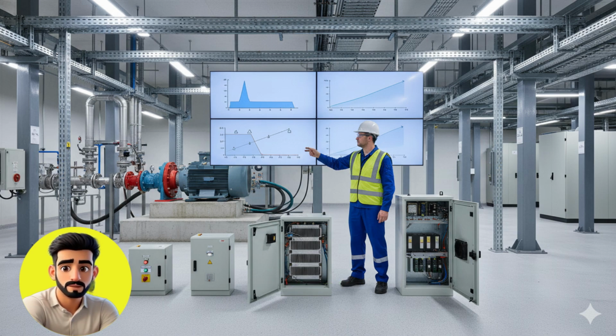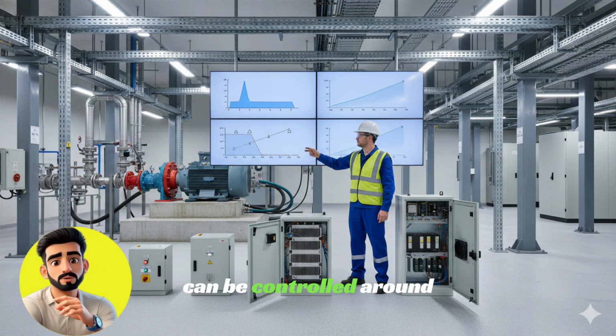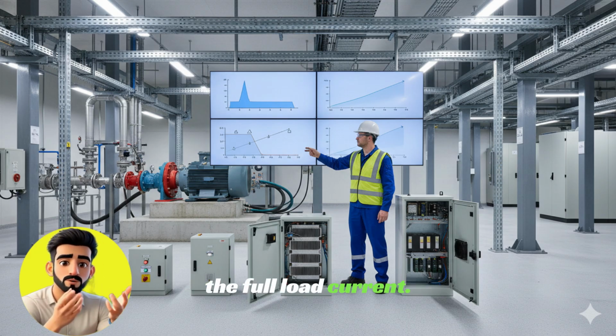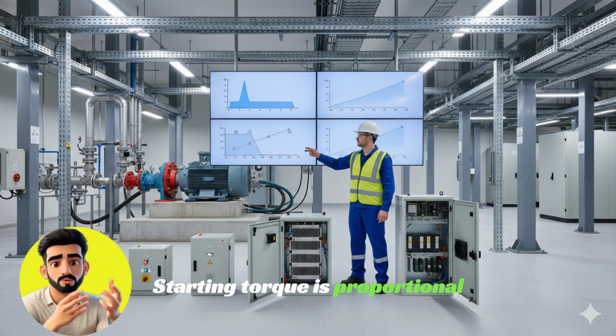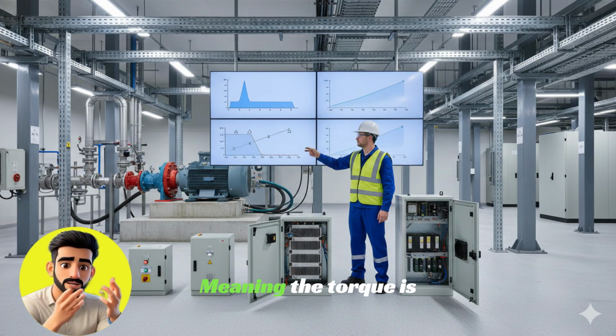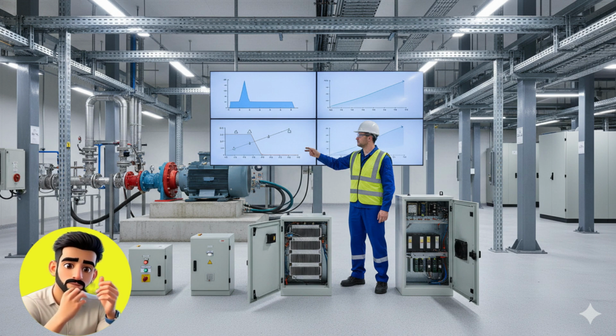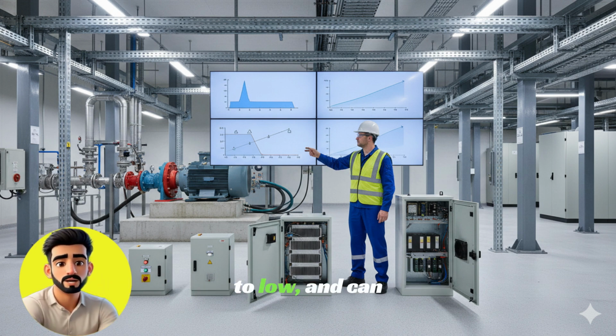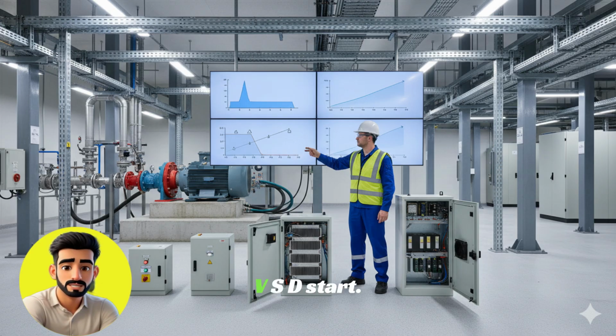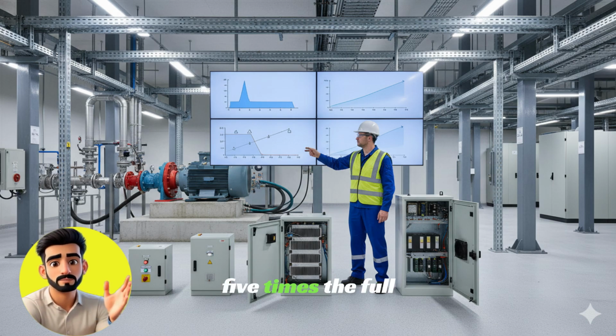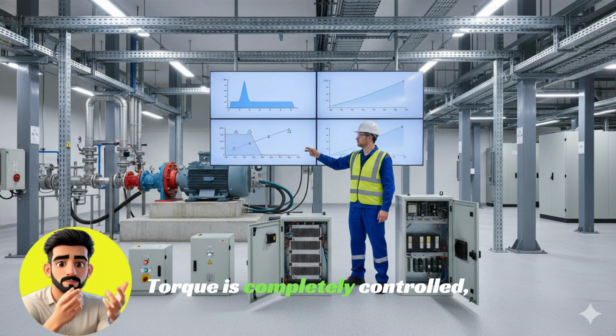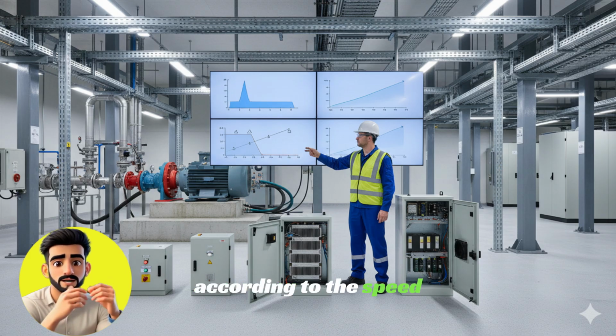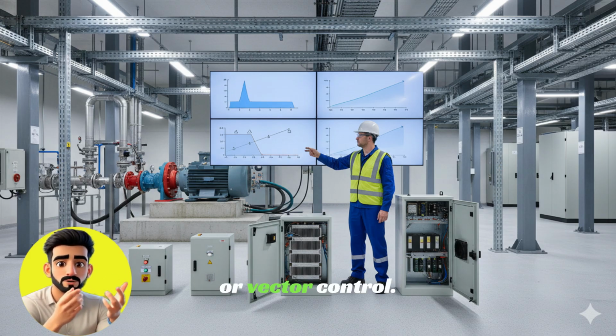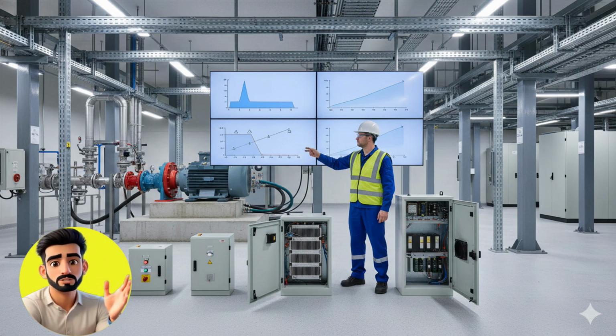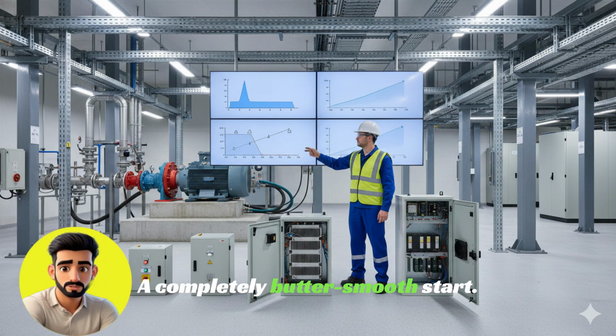Soft starter. Here, the starting current can be controlled around 3 to 4 times the full load current. Starting torque is proportional to the square of the voltage, meaning the torque is also smooth. Mechanical shock is medium to low and can also be adjusted. VSD start. Starting current is normally 1 to 1.5 times the full load current. Torque is completely controlled according to the speed and through V/F control or vector control. Mechanical shock is almost zero, a completely butter smooth start.